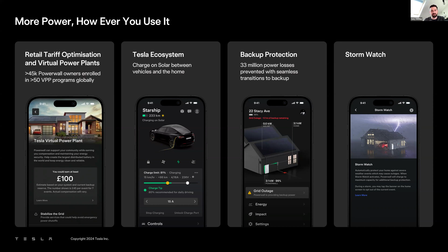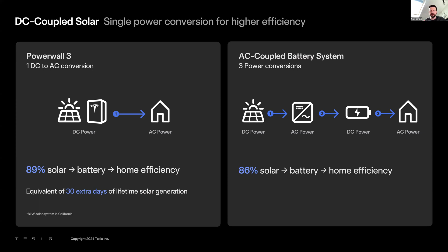Now, what we're trying to do with Powerwall is increase the overall efficiency of the system. With Powerwall 2, there were 3 power conversions because it was an AC coupled system - DC to AC, DC to AC - giving 86% efficiency, and we looked at how to improve that. So we've moved to a DC coupled architecture, which drives an extra 3% efficiency. That doesn't sound like a lot, but it's the equivalent of an extra 30 days of lifetime solar generation - these small percentages add up to greater savings for your end customers.